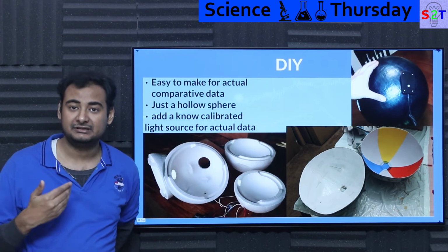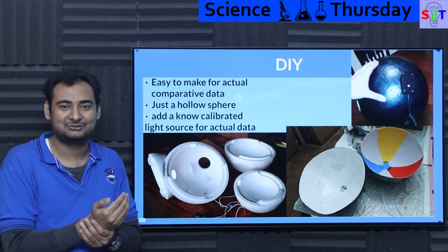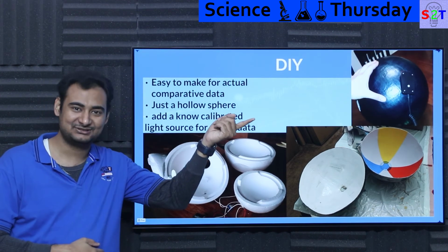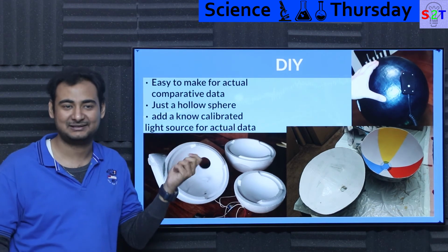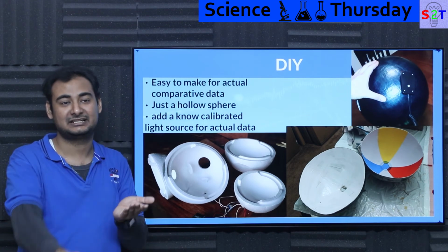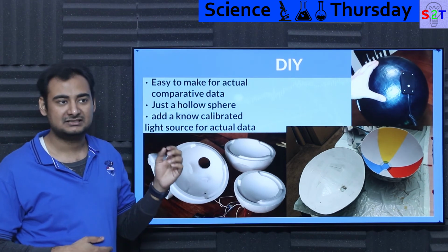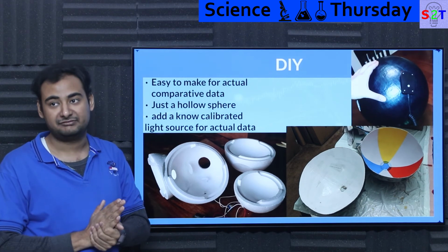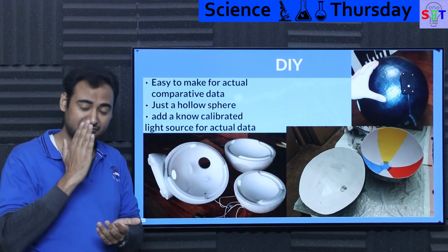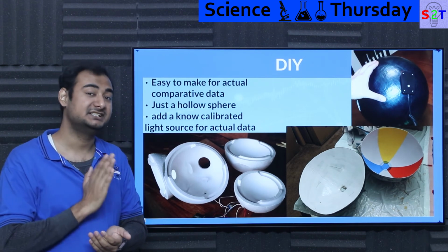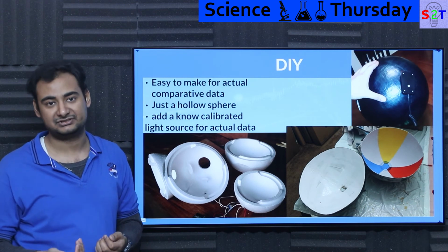And even in this sort of environment, people are like, how about we make it more accurate? They generally try to find a quote unquote friend who works in an association like the Bureau of Standards, and they ask, can you calibrate this flash lamp? And it's like, okay, this lamp is tested and calibrated. Or sometimes people buy known brands. If a brand is certifying it, the brand could itself have their own integration sphere, and if they say 500 lumens output, it means it has 500 lumens output, and you can use that as a calibration for your sphere.